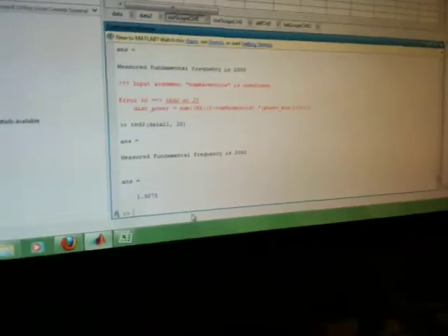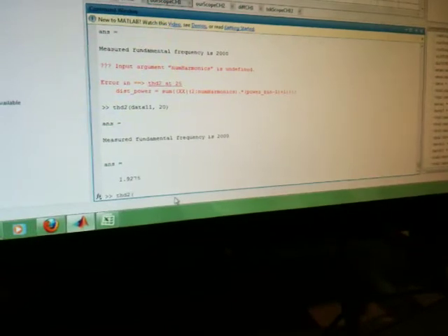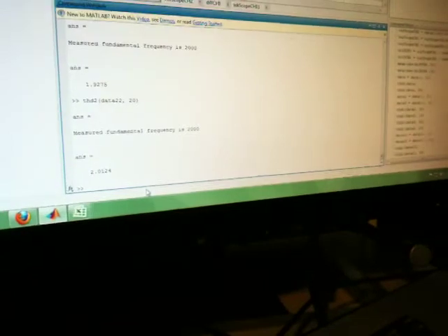Now we'll take a nice little THD calculation of the first sample, the baseline sample. And, oops, I have to define how many harmonics we want to calculate it for. We'll do 20 harmonics. That should be sufficient. And it gives us a nice fundamental frequency, which is 2 kilohertz, like we would have expected, and we have 1.9% total harmonic distortion, still well below our 5% value that we are always shooting for. Now let's calculate it for our second signal with also 20 harmonics, a little higher as you would expect with a blender on nearby, about 2% total harmonic distortion, still well below 5%.